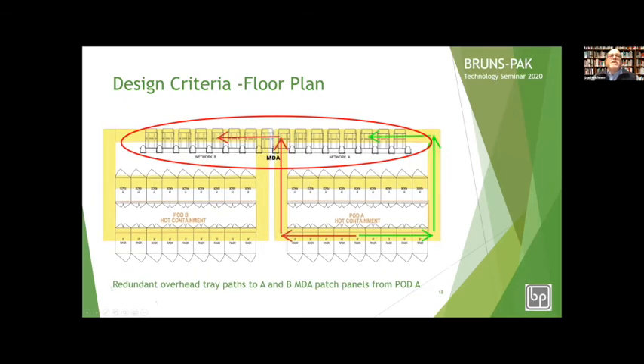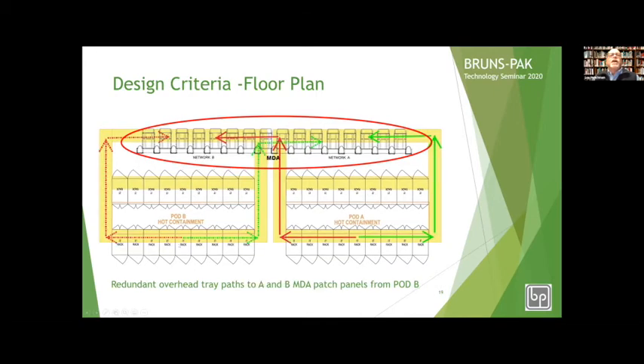The tray paths are redundant. From Pod A and Pod B, every rack has a redundant tray path to the MDA. For example, an IT cabinet goes out one way to reach Network A, and down another path to Network B — cables completely in redundant overhead paths. The matching rack in Pod B comes down a different path into the MDA. Completely redundant cable paths — 2,600 square feet, 36 IT racks.